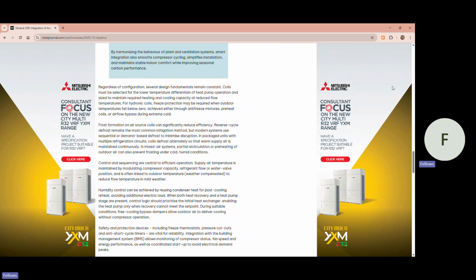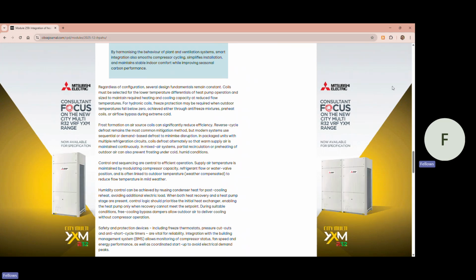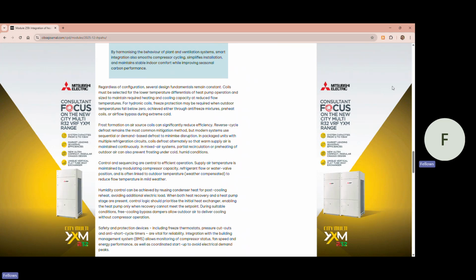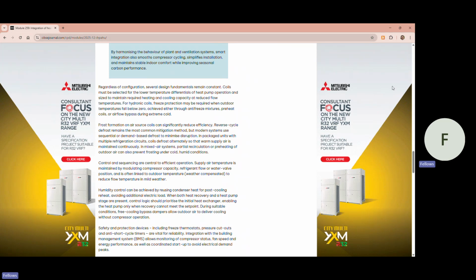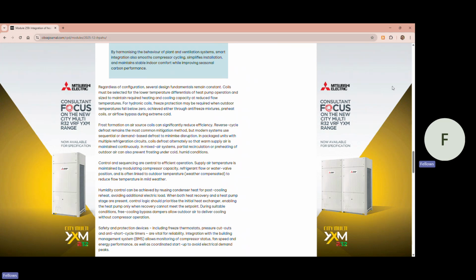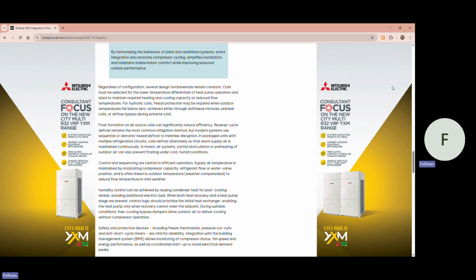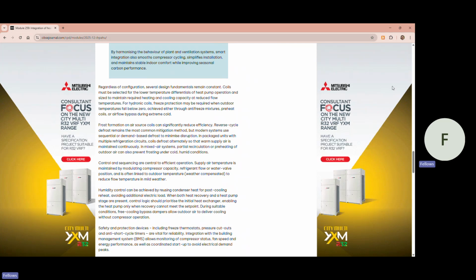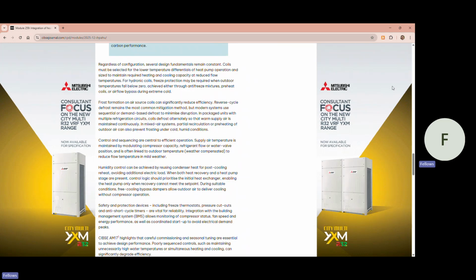Frost formation on air source coils can significantly reduce efficiency. Reverse cycle defrost remains the most common mitigation method, but modern systems use sequential or demand-based defrost to minimize disruption. In packaged units with multiple refrigeration circuits, coils defrost alternately so that warm air supply is maintained continuously. In mixed air systems, partial recirculation or preheating of outdoor air can also prevent frosting under cold, humid conditions.